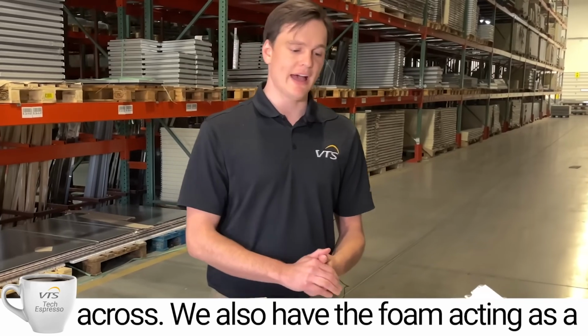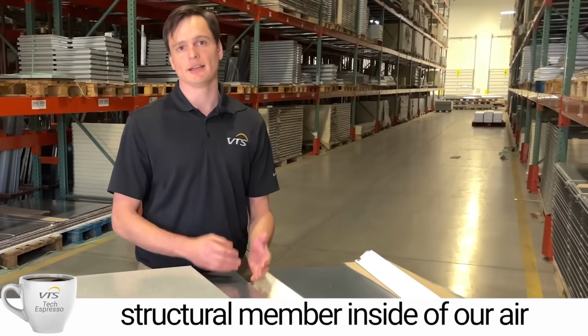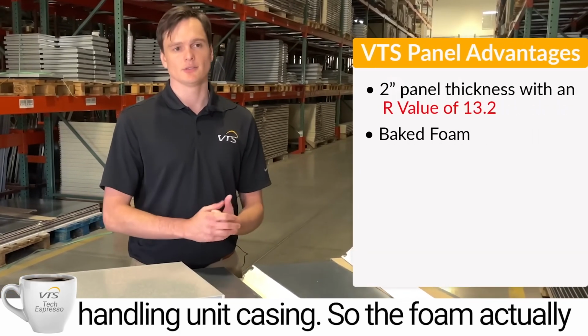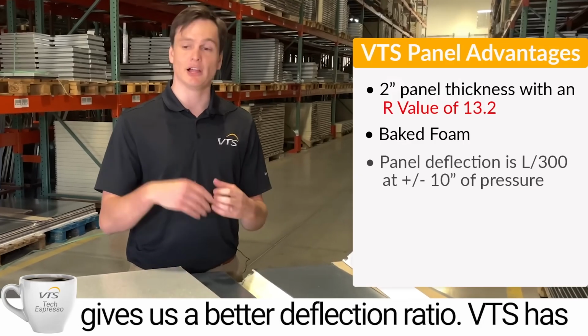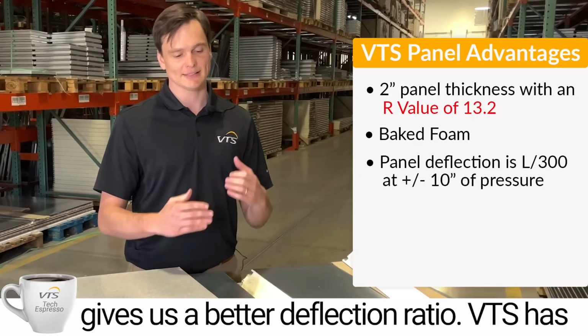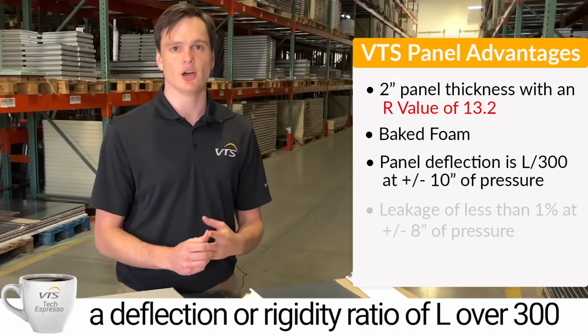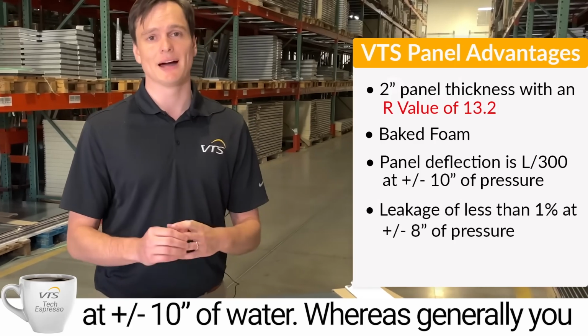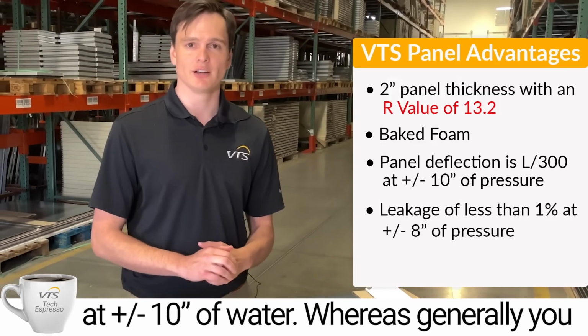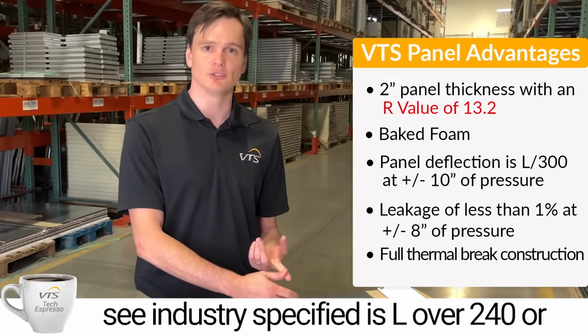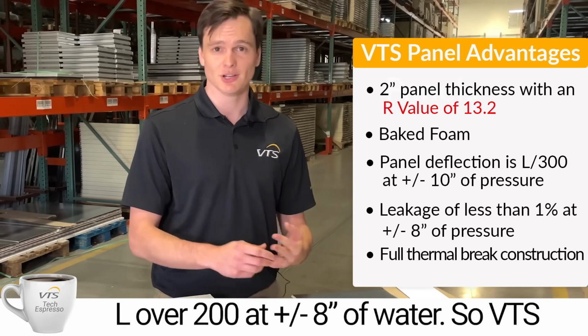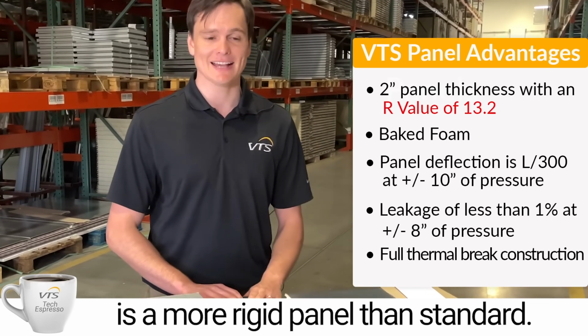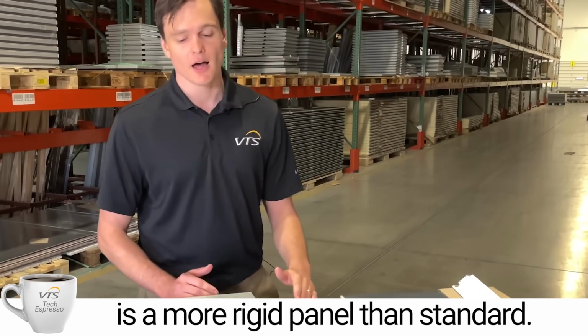We also have the foam acting as a structural member inside of our air handling unit casing. So the foam actually gives us a better deflection ratio. So VTS has a deflection or rigidity ratio of L/300 at plus or minus 10 inches of water, whereas generally you see industry specified as L/240 or L/200 at plus or minus 8 inches of water. So VTS is a more rigid panel than standard.